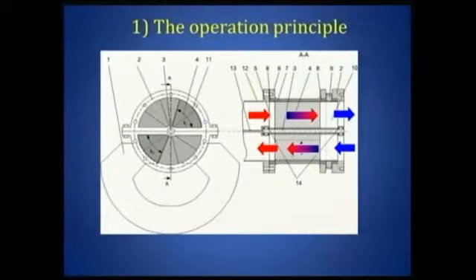For these people who don't know how magnetic refrigeration operates, I have here a little picture which shows very nicely the principle. You see underneath, on the left, a magnet. So this creates a magnetic field in the lower part, and in there we have a porous cylinder turning, like, probably you know, rotative heat exchangers in air conditioning. So we can flow through with a fluid through the lower part and with another fluid through the upper part, half circle, and we have a part which is not in the magnetic field.